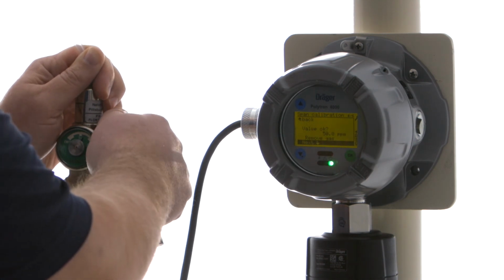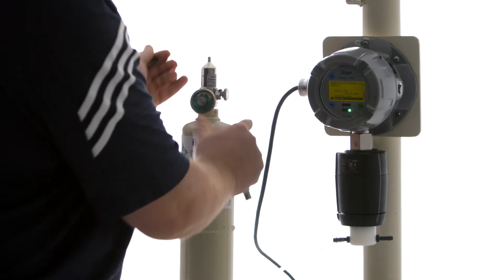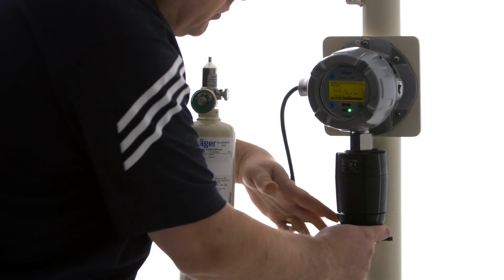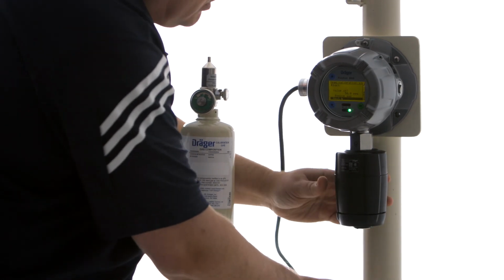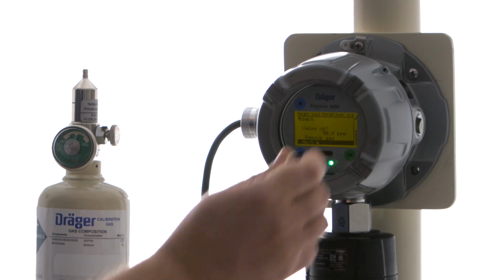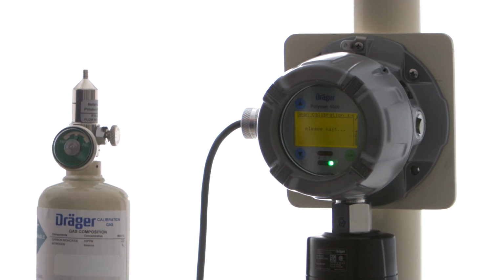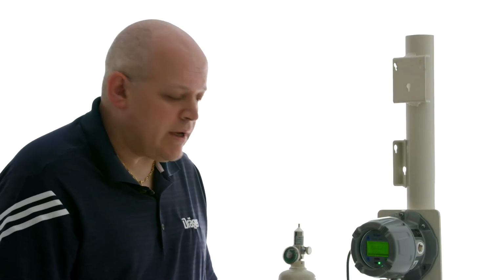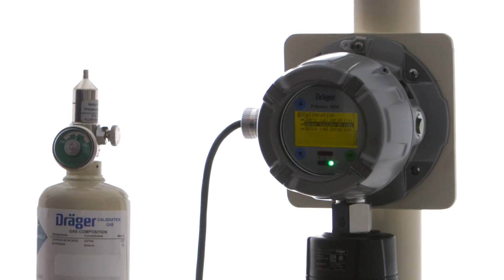Now it's asking us to remove the gas. So I'm going to remove the cup. And we're going to select next. And now it's asking us if we're out of alarm range. So whatever your alarm limits are, make sure the value that is showing here is below that. And then we can select next, and we're done with our span calibration.